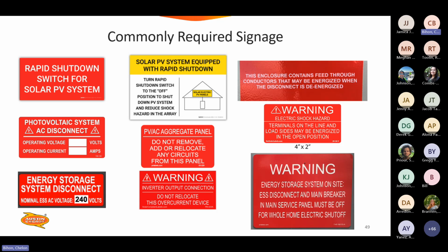Common required signage. Rapid shutdown switch for solar PV system. Photovoltaic system AC disconnect. It's got the volts and the amps. Energy storage system disconnect. That's one that's often missed. Solar PV system equipped with rapid shutdown. PV AC aggregate panel. Do not remove and/or relocate any circuits from this panel. We don't permit loads on the PV side of our DG services. That sticker is important.